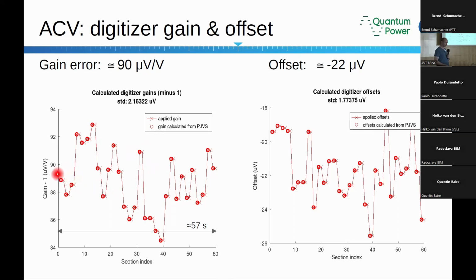But always there is a section of Josephson when the gain is calculated, then after the multiplexer switch there is a section of the calibrator. So we apply this gain calibration to the next section. Then again, we measure Josephson, calculate a new gain, apply it to the next section when the calibrator was measured, and so on and so on.